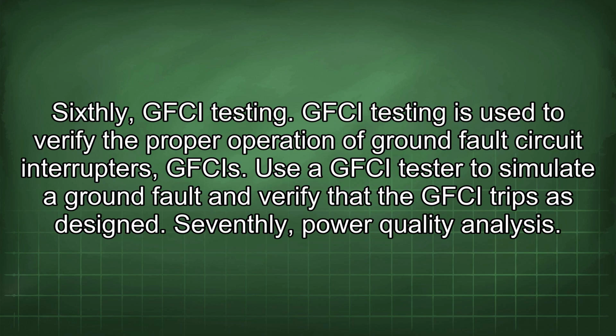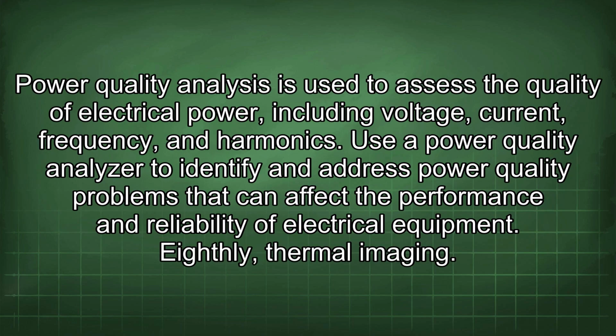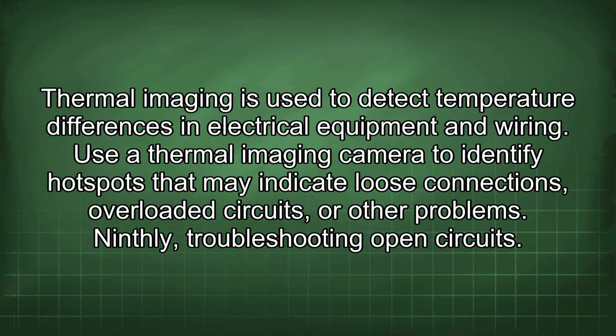Seventhly, power quality analysis. Power quality analysis is used to assess the quality of electrical power, including voltage, current, frequency, and harmonics. Use a power quality analyzer to identify and address power quality problems that can affect the performance and reliability of electrical equipment. Eighthly, thermal imaging. Thermal imaging is used to detect temperature differences in electrical equipment and wiring. Use a thermal imaging camera to identify hotspots that may indicate loose connections, overloaded circuits, or other problems.